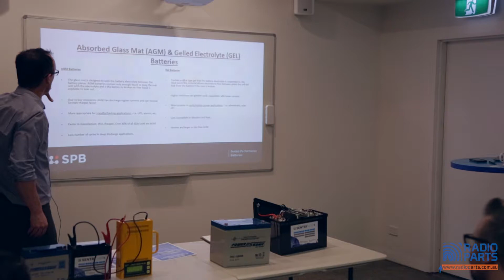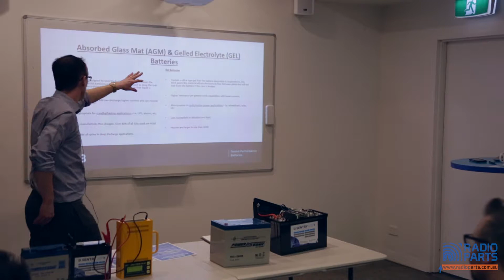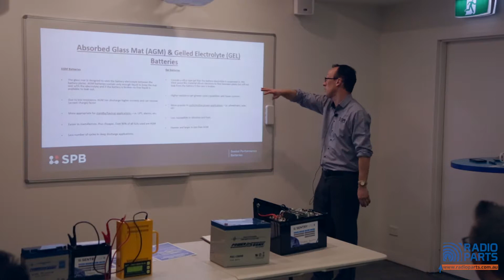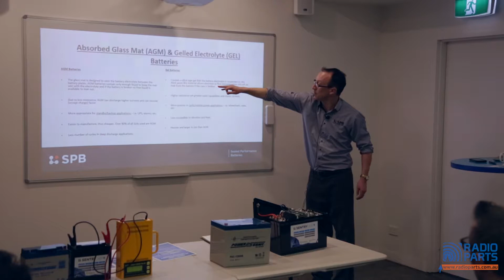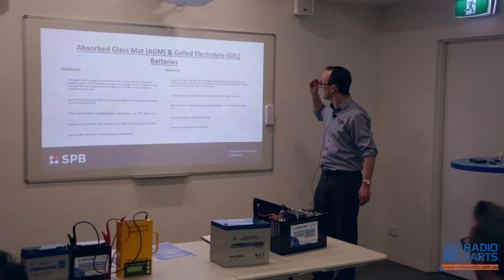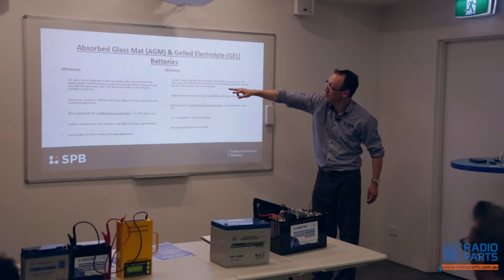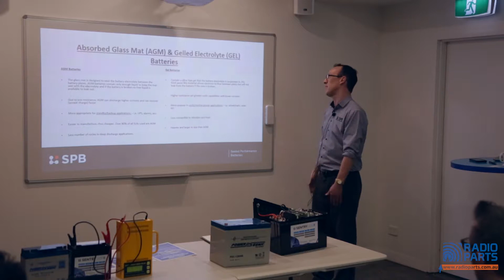With AGM batteries, it's purely water and sulfuric acid combination. When it comes to gel batteries, they add silica, like a silicon or sand-based material, to the electrolyte mix. When they add silica, it forms a paste, meaning the electrons are absorbed slower into the plates, whereas in AGM batteries it's faster with less resistance. As a rule of thumb, AGM batteries are more appropriate for standby applications, while gel electrolyte batteries are more appropriate for cyclic applications. That's the main difference between the two.